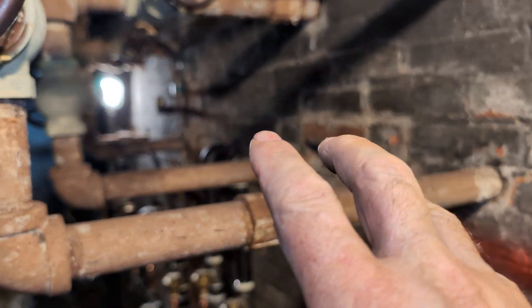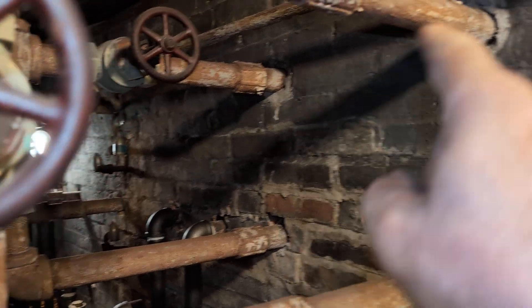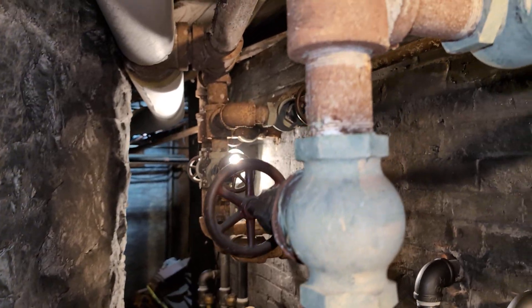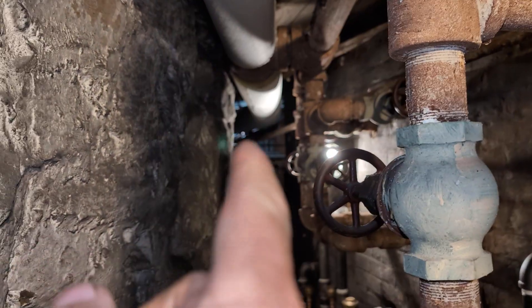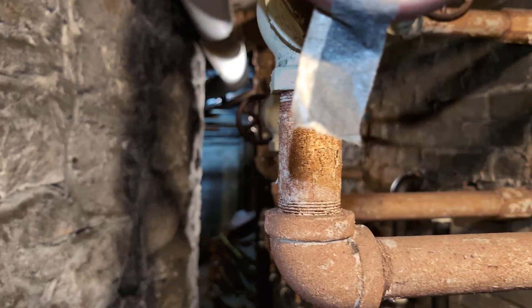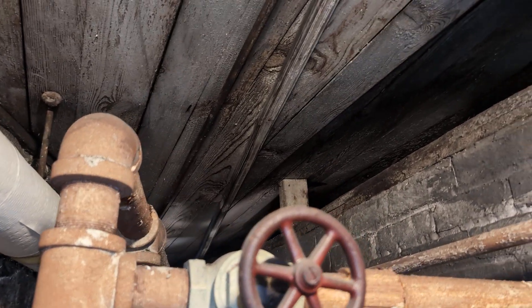These are the steam supplies — you have a total of eight: four here and then four at the other end, tied off a two-and-a-half-inch manifold, which then comes off one of the several steam mains that feed the undercroft of this sort of amphitheater-like sanctuary located above.